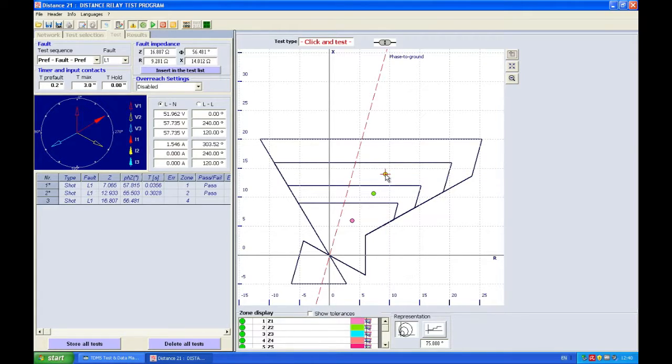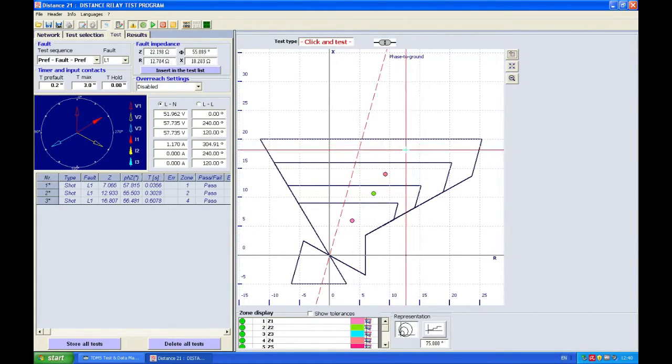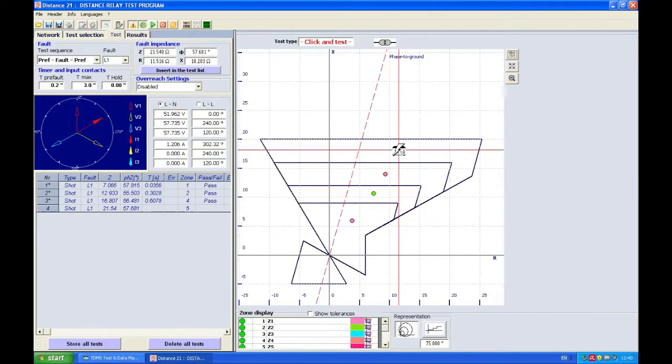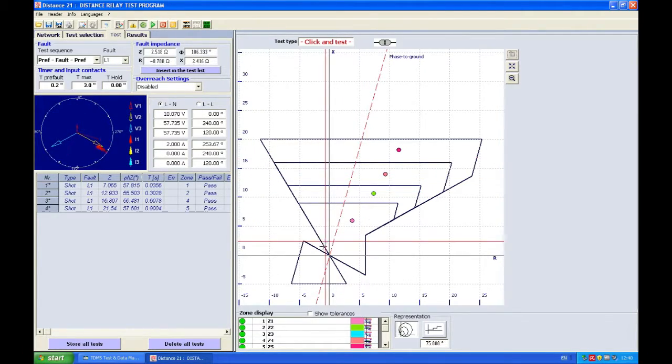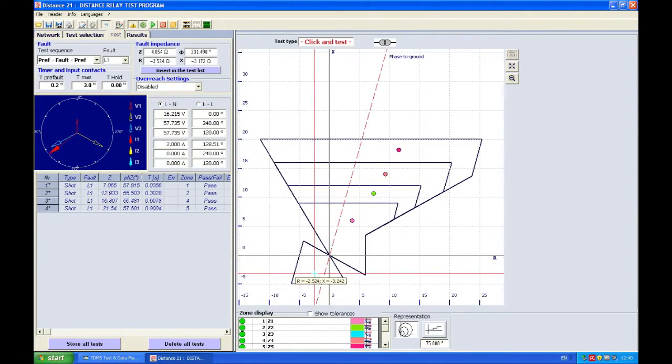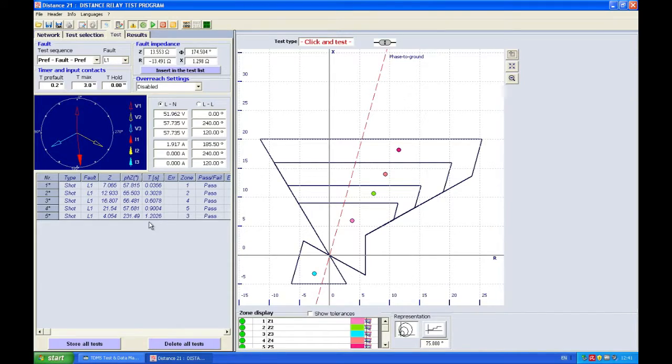If I click here I expect tripping in 600 milliseconds. I got 607.8 which is still a pass. Zone 5 should trip in 900 milliseconds so I got 900.4 and this is okay. I will trip also zone 3 which is in the back to see the tripping in 1.2 seconds and actually it's 1.2026 which is of course a pass.